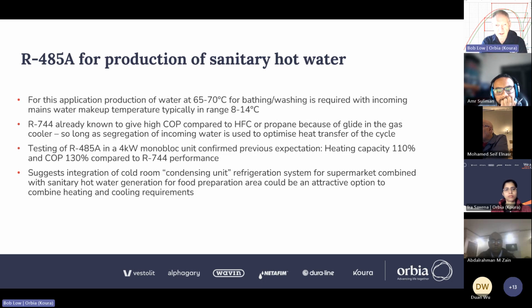When we ran the monoblock, we ran a domestic hot water point, and we found COP and capacity gains compared to CO2. So with the more sophisticated condensing unit, with its twin stage compression technology and potential for even higher COP gain, that suggests that integration of a condensing unit for a cold room or a walk-in freezer to the hot water supply for supermarket food prep area could really be quite an attractive option that would let you do heat integration across the store more efficiently and would also give you nice hot water at a low COP and at the same time as cooling at a high COP.